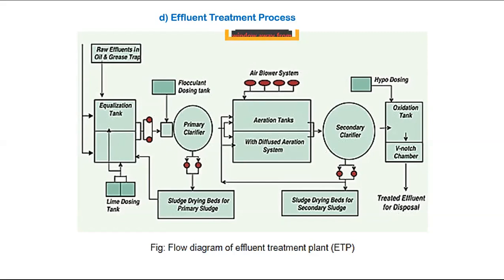So first you have to arrive at the total water demand, the one day water demand. From the one day water demand, you have to take the 90% diversity factor for the STP. After that, for the output water, you have to take 80% of the input water. That is the concept. This may vary based on the practical condition.